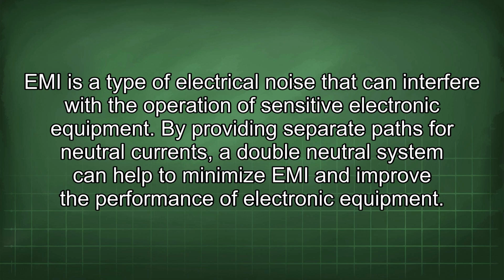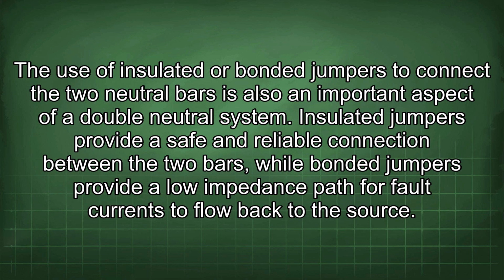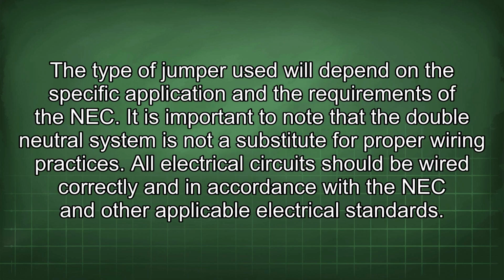The use of insulated or bonded jumpers to connect the two neutral bars is also an important aspect of a double neutral system. Insulated jumpers provide a safe and reliable connection between the two bars, while bonded jumpers provide a low impedance path for fault currents to flow back to the source. The type of jumper used will depend on the specific application and the requirements of the NEC.